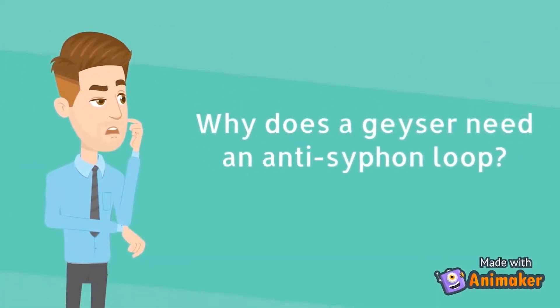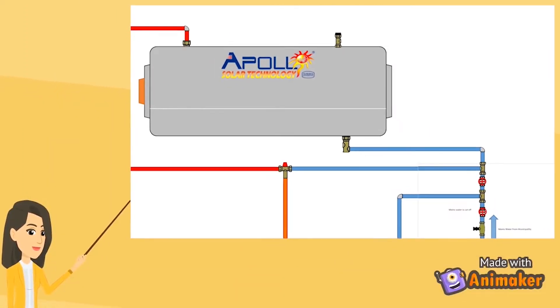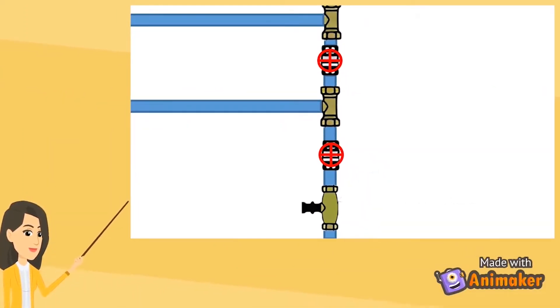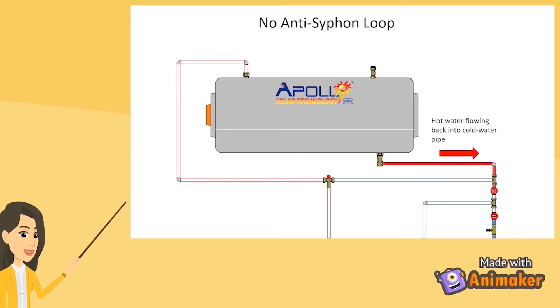So, why does a geyser need an anti-siphon loop? Well, when a geyser is installed without an anti-siphon loop and the main water supply is cut off, hot water is sucked out of the geyser through the cold water inlet and siphoning occurs, causing the geyser to drain itself.